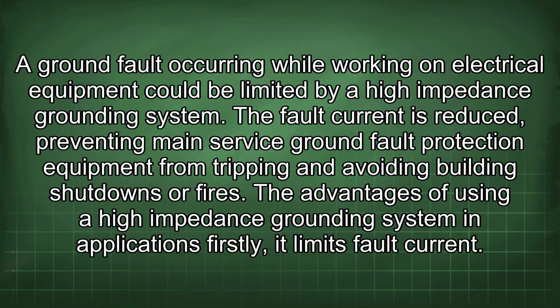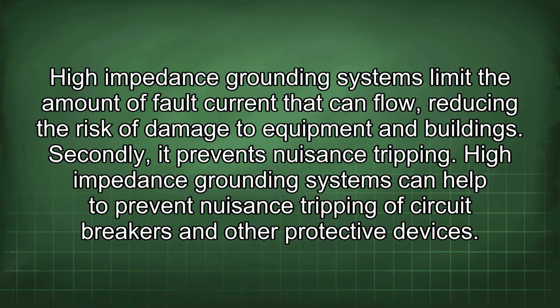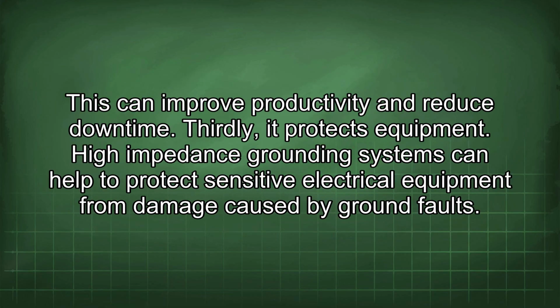The advantages of using a high-impedance grounding system in applications: firstly, it limits fault current. High-impedance grounding systems limit the amount of fault current that can flow, reducing the risk of damage to equipment and buildings. Secondly, it prevents nuisance tripping. High-impedance grounding systems could help to prevent nuisance tripping of circuit breakers and other protective devices. This can improve productivity and reduce downtime.